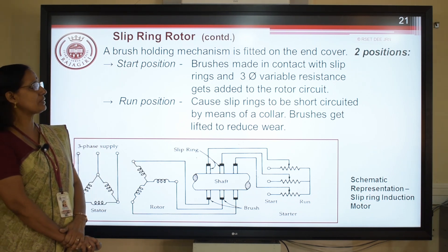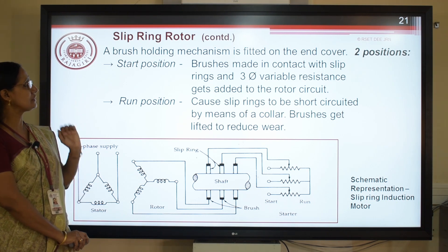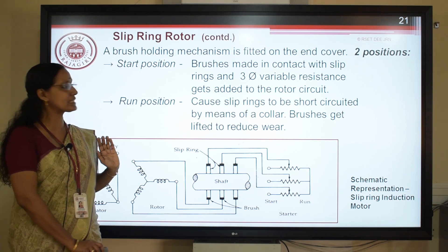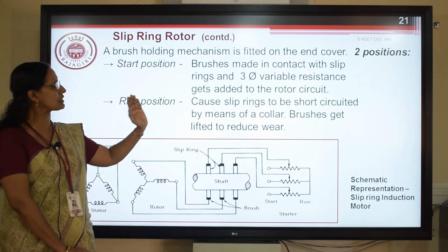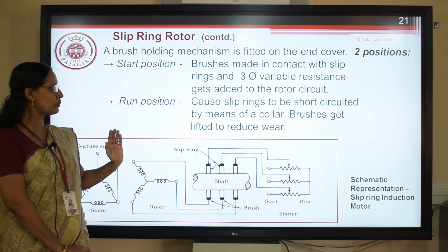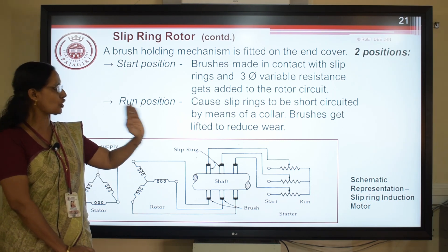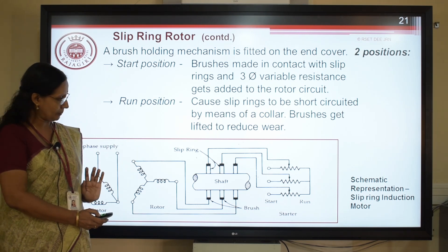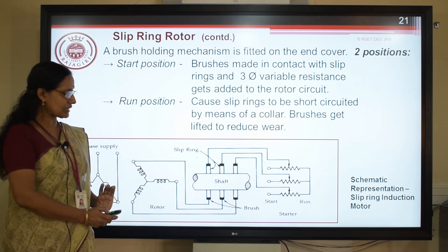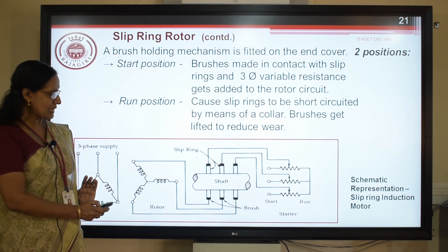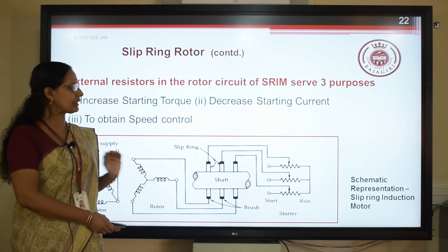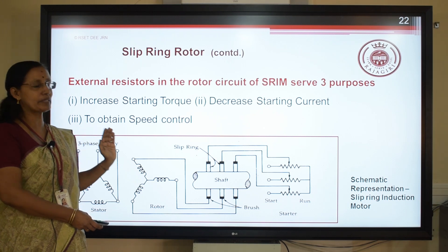A brush holding mechanism is fitted onto the end cover. It has two positions: the start position and the run position. In the start position, the brushes come in contact with the slip rings and the three-phase variable resistance gets added to the rotor circuit. The run position causes the slip rings to be short-circuited by means of a collar, and the brushes also get lifted to reduce wear. The figure shows the schematic representation of a slip ring induction motor. The need for external resistors is to increase starting torque, decrease starting current, and to obtain speed control.